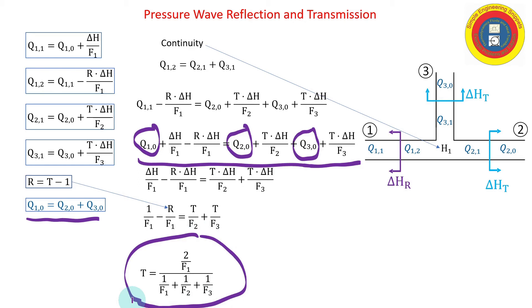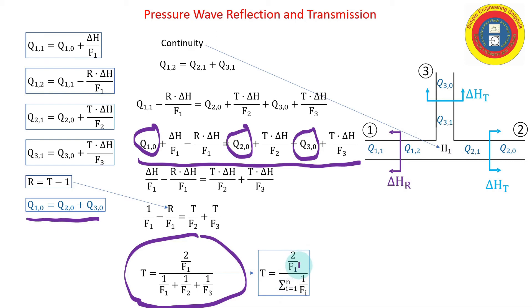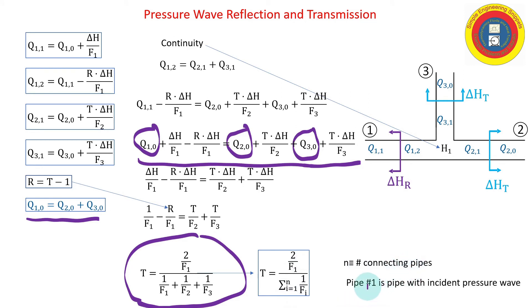Substituting R equals T minus one and solving, we get the transmission factor. For a general n-pipe junction, the transmission factor is: T equals two divided by F1, all over the sum from i equals one to n of one over Fi, where n is the number of connecting pipes and F1 is the elastic factor for the pipe carrying the incident pressure wave.